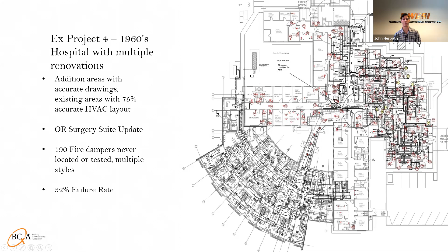I think this one had a 32% failure rate. It was just huge. And the high failure rate is especially troublesome when they're fire dampers, because they all need to get replaced, and it's very expensive to replace those versus swapping out a motor, which is usually pretty easy.